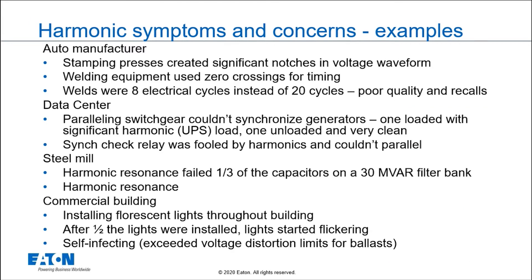We have a couple of case study examples here. In the first one, there was significant voltage notching, and the welds on minivan tailgates were not substantial — instead of being 20 electrical cycles long, they were only 8 cycles, requiring a recall due to poor welds. In the data center case, we couldn't parallel a couple of generators — one loaded, one unloaded — because harmonic voltage distortion caused issues with the transfer switch and the relay scheme doing the paralleling.